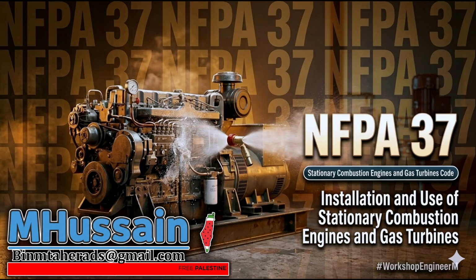To bring all this theory into the real world, I want to talk about that case study from EPC land. Ah, yes. The commissioning inspection. It's a perfect example of what goes wrong in the field. So the engineering team shows up for a final inspection on a new facility, and they find the outdoor generator is installed only 3 feet from a combustible wood-framed wall. Which is a direct violation of the 5-foot clearance rule we discussed earlier.